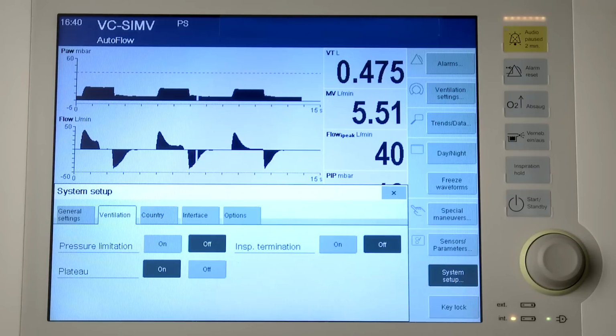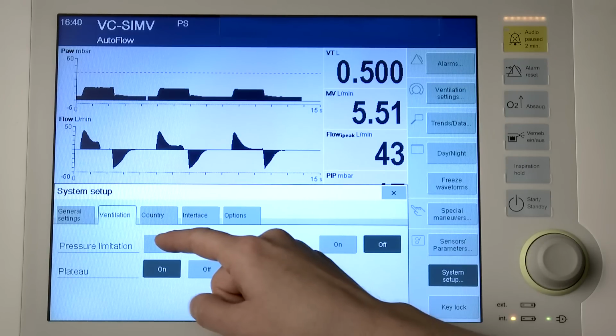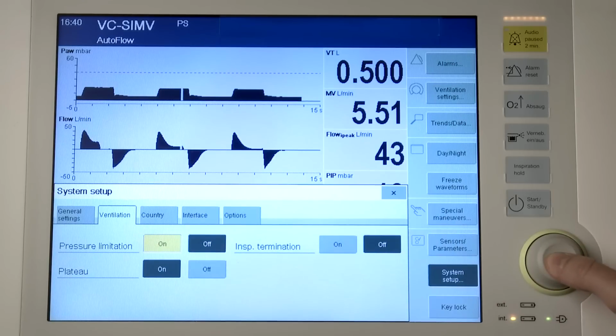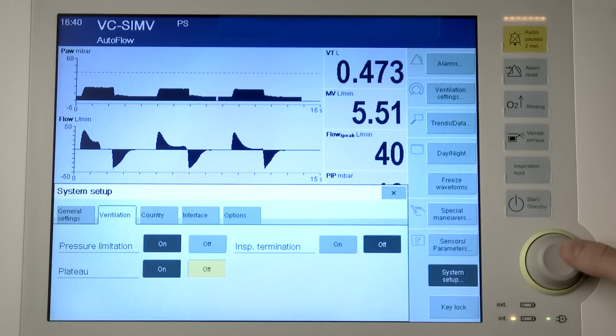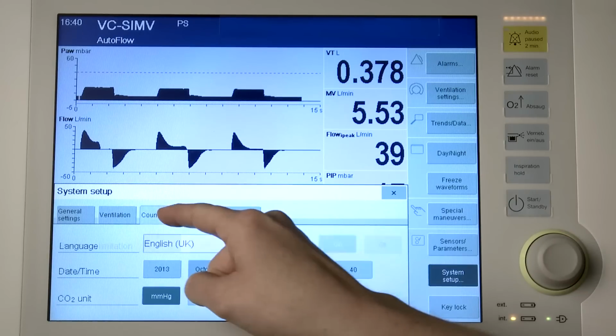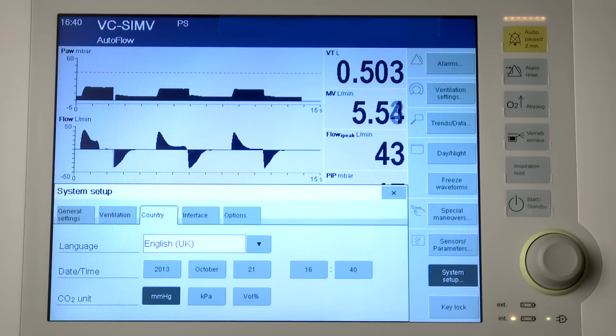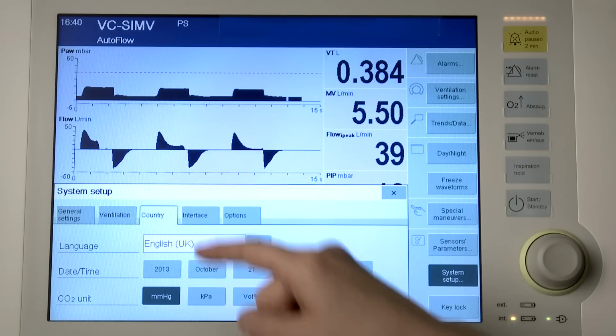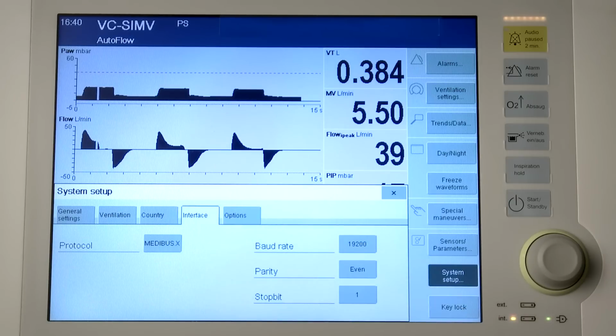On the ventilation page, the ventilation functions pressure limitation, inspiratory pause, time plateau, inspiratory termination, and, if available, low-pressure oxygen LPO can be activated or deactivated. Touch the on or off button and confirm with the rotary knob. You can configure a language, the date and time, and the units on the country page. Data exchange takes place via Medibus or nurse call.